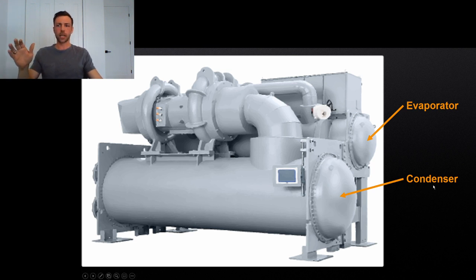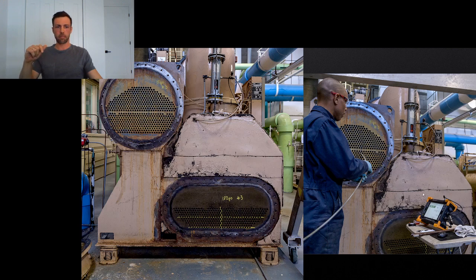Similar to what you would see in oil and gas, petrochem, or BOP, these heat exchangers need regular maintenance. They need to be opened, cleaned, inspected. This picture shows the tube sheet of the evaporator at the top and the condenser at the bottom, with the cover removed. They have been cleaned and are now ready to be inspected by a technician, as you can see on the right.